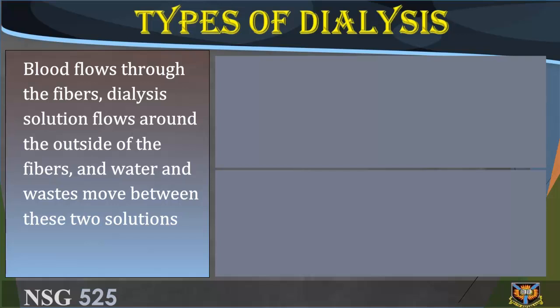The levels of these components of dialysate are typically prescribed by a nephrologist according to the needs of the individual patient. The cleansed blood is then returned via the circuit back to the body. All filtration occurs by increasing the hydrostatic pressure across the dialyzer membrane. This usually is done by applying a negative pressure to the dialysate compartment of the dialyzer. This pressure gradient causes water and the soft solute to move from blood to dialysate and allows the removal of several liters of excess fluid during a typical 4-hour treatment.